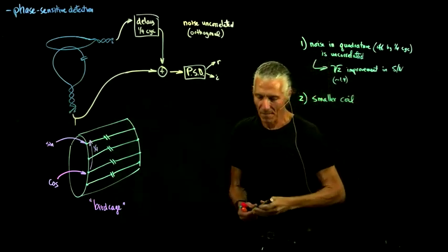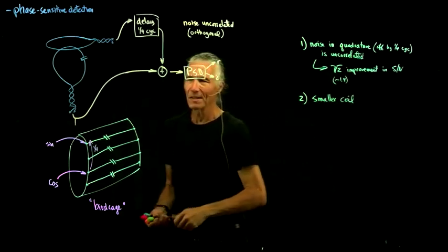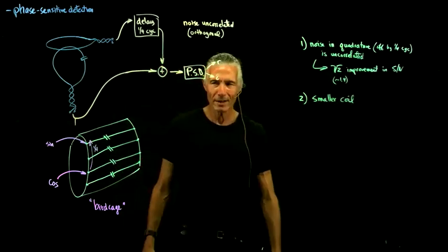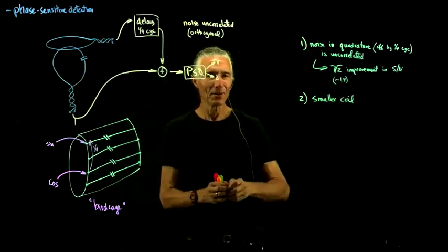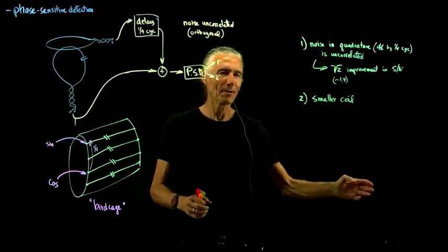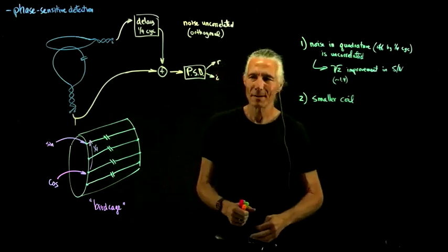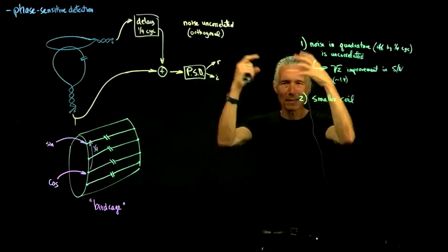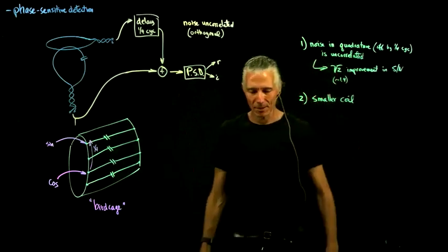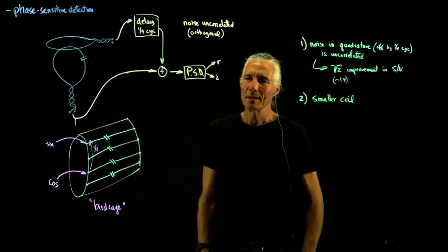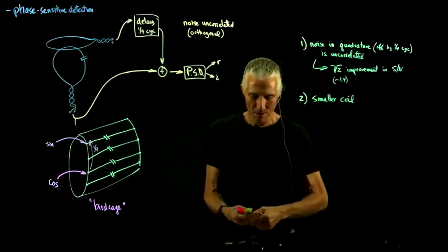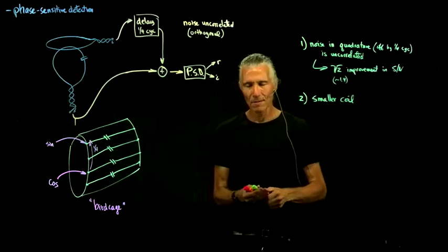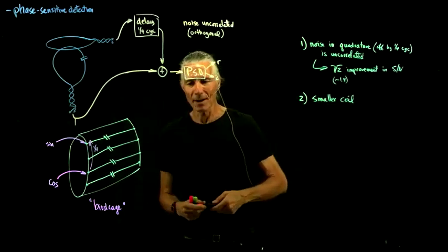But now here's the issue. We're talking about radio waves, and radio waves just kind of come out of the head and go a long distance, like they go right across the bore, no problem. They go out into the room, come out of your head, and go into the coil, but they go everywhere. So if you think about that, what's the best way to record radio waves? Well, make a big antenna. And it turns out the body coil is a nice honking big antenna.